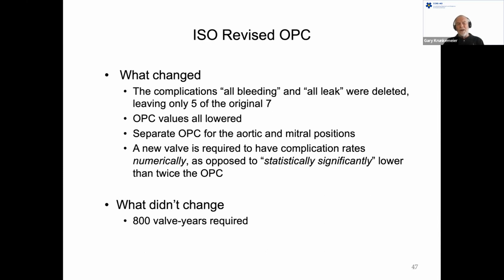And a very important change was that a new valve no longer had to be statistically significantly lower than twice the OPC. It just had to have its average lower than twice the OPC, not statistically lower. So those confidence intervals shown in all those figures, those little up and down whiskers, didn't have to be below two times the OPC, just the average value, the little symbol in the middle, had to be lower. I guess that seems like a compromise, but it was necessary in order to make these new values workable.